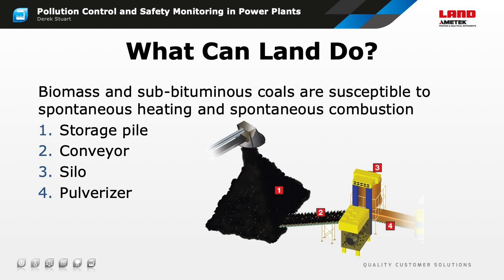Several technologies are available to detect spontaneous combustion and give early warning before it develops into a fire. Today, I shall concentrate on the instruments manufactured by AMETEK Land, but of course we are not the only supplier with this type of equipment. Thermal imaging is ideal for measurements on open or semi-enclosed storage areas such as coal piles and biomass storage domes. Infrared scanners can detect small amounts of overheating material on a conveyor belt, and carbon monoxide monitors can detect the CO emitted as fuel oxidizes within an enclosed space such as a silo or a pulverizer.